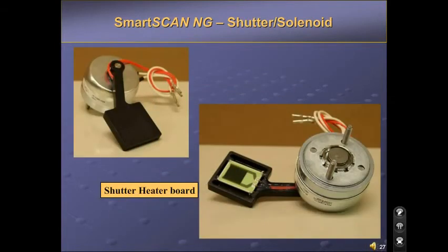The shutter solenoid mechanism performs two functions, keeping debris out of the scanner and post-train integrity testing. As a train enters a location, the shutter door opens. The resistive heaters will begin to heat when the shutter is activated. The door stays open through the entire train. After the train has passed, the shutter door closes and the system samples the heat from the shutter resistor. This sample is compared to a preset limit. If the resistor sample exceeds the limit, the integrity test is passed. If it is below the limit, the system will call it a cold resistor.